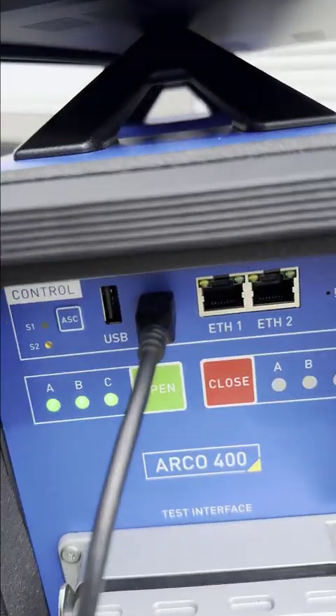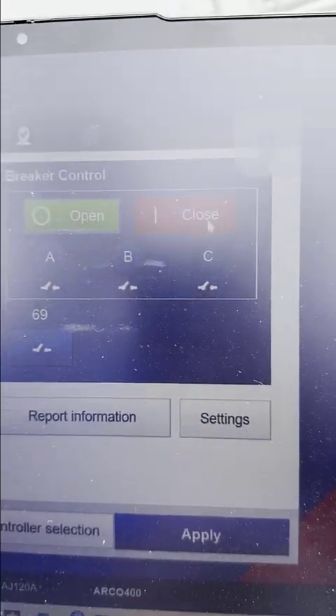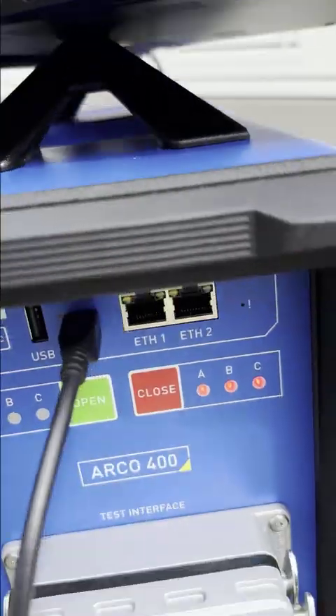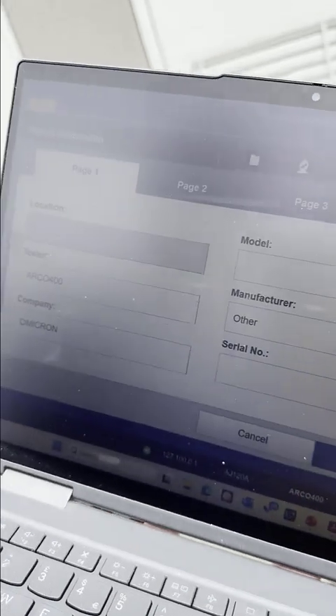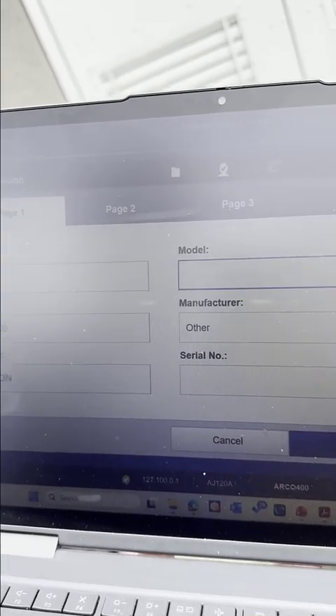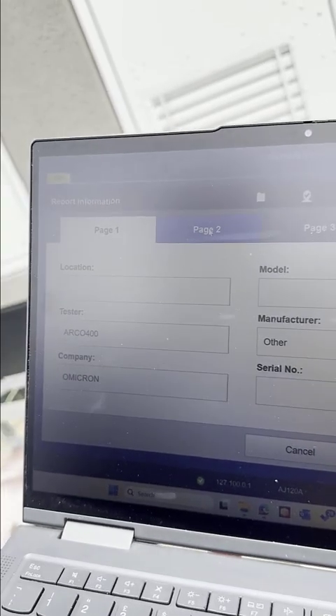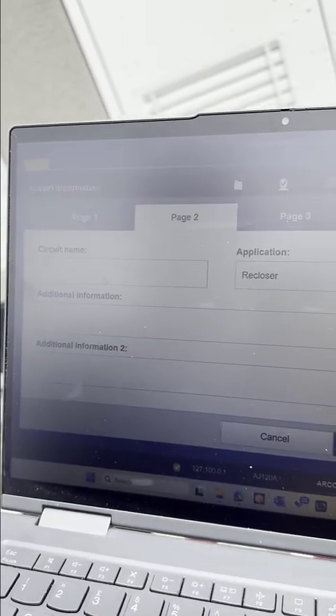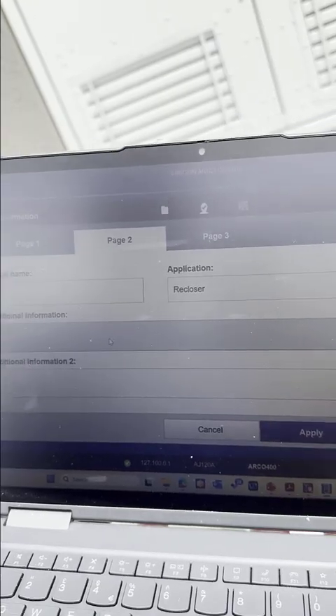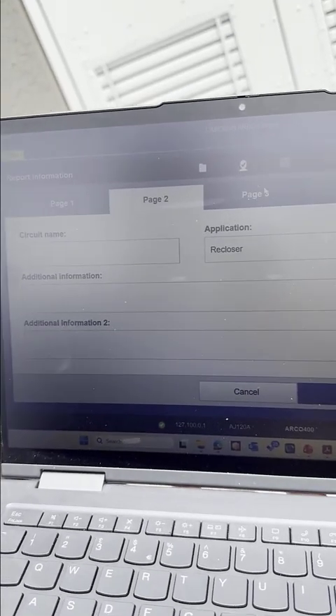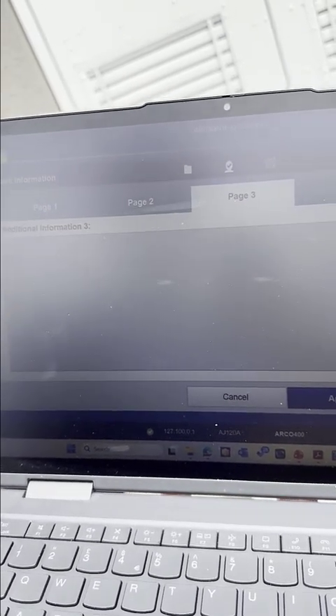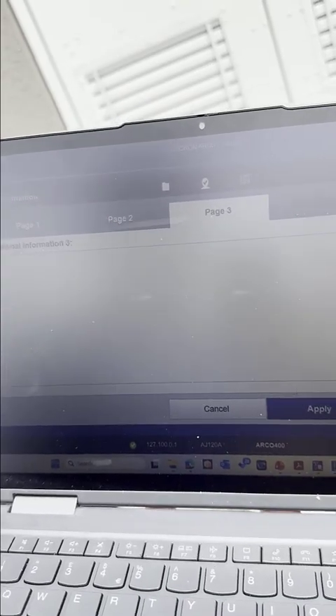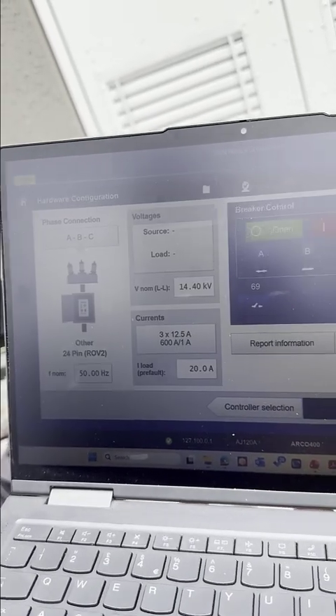So simply you can also give an open command and close command, and you can check the indication from the front panel or from this contact, as you can see from here. Then you can define the report information: the location, the model, the serial number, the company, and so on. Also you can enter any values or additional information you need to be printed out in your test result. As you can see, for additional information 2, you have a bigger box to enter whatever you need to be printed out in your test result.